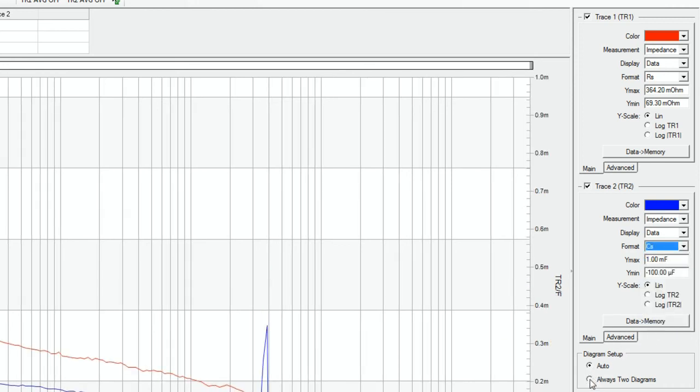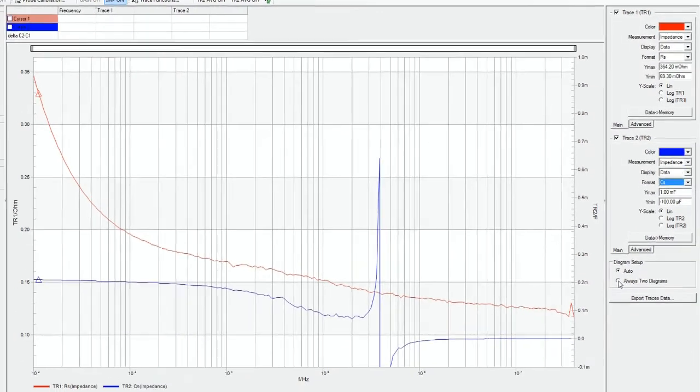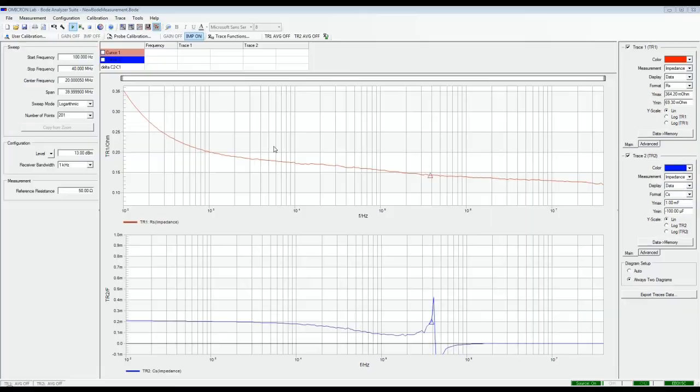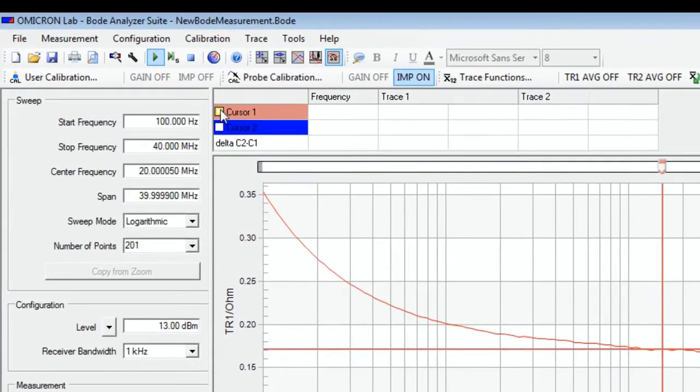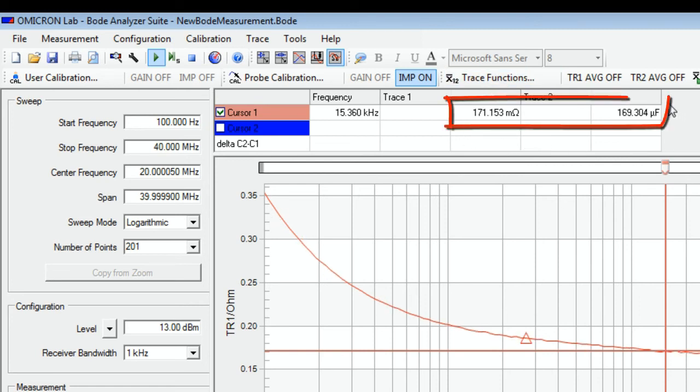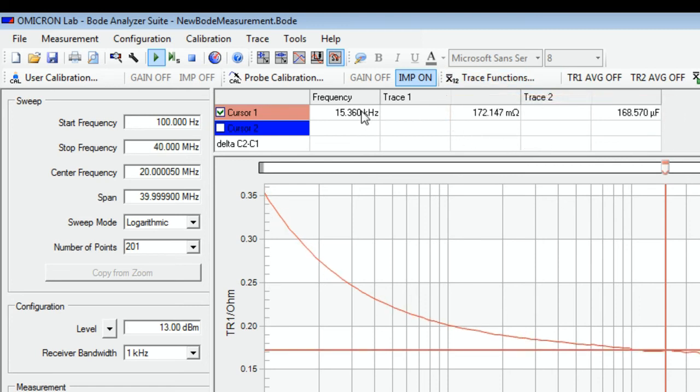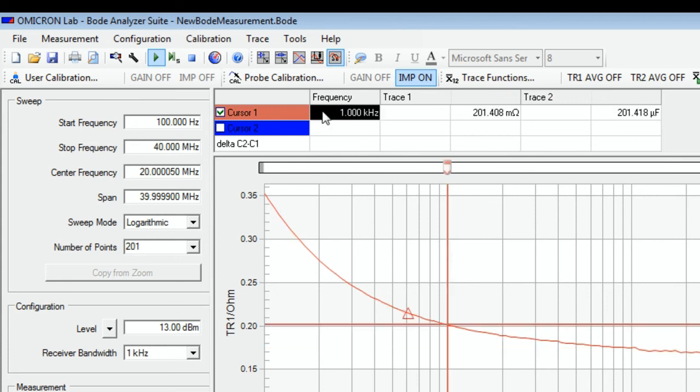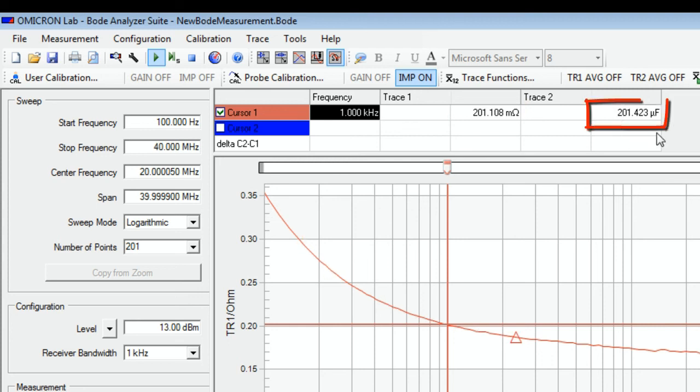We can choose to show these curves in two diagrams. Now we can set the cursor and measure the series capacitance and resistance for example at 1 kHz. At 1 kHz we have a series resistance of 201 milliohm and a series capacitance of 201 microfarad.